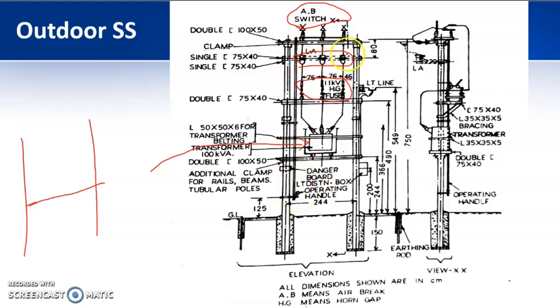Then you will be having your lightning arrestor, and from this lightning arrestor it is coming to the horn gap fuse, the 11 kV horn gap fuse. The fuse element will be there, and then it is coming to the transformer high voltage bushings. You'll be having the 3 high voltage bushings, you can see it over here. And from there you will also have your low voltage bushing on the other side of your transformer. From there it is taken through a 3.5 core cable to your LT distribution box. So this is nothing but an LT distribution box. From there it is taken to your inside system. You'll be having your LT switchboard there, and you'll be using that.